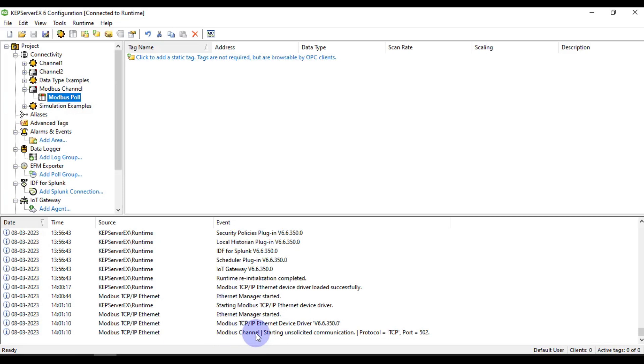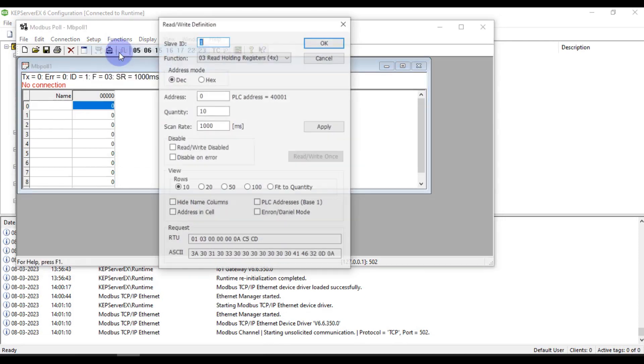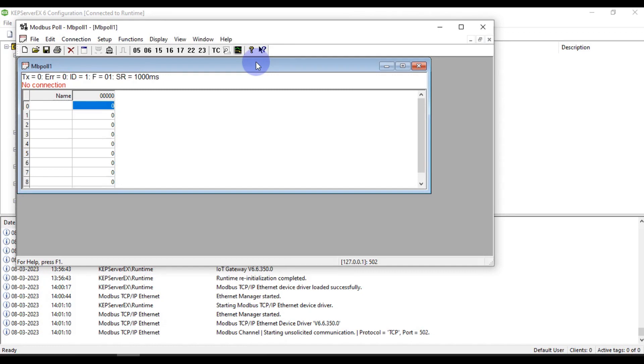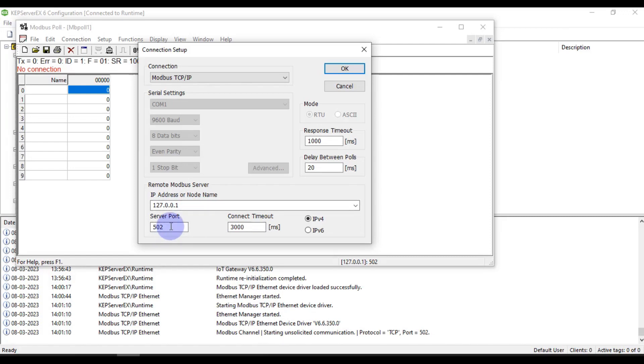You can see Modbus channel starting unsolicited communication, protocol TCP, port number 502. Now we can go to our Modbus Poll software. Go to Setup and click on Read/Write Definition. Here we have to choose our slave ID — slave ID is 1. Then we are going to select a function as Read Coil, or output coils. The quantity we want is 10, then press OK. Now go to Connection and press Connect. Set port number 502, connection is Modbus TCP/IP, IP address is the local host IP address, then press OK.